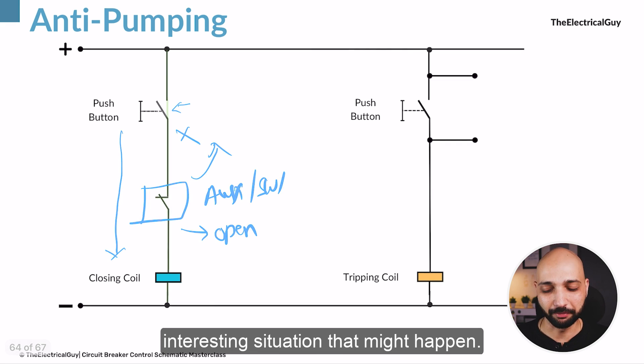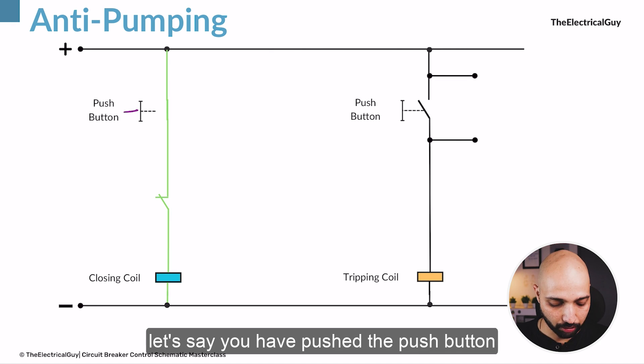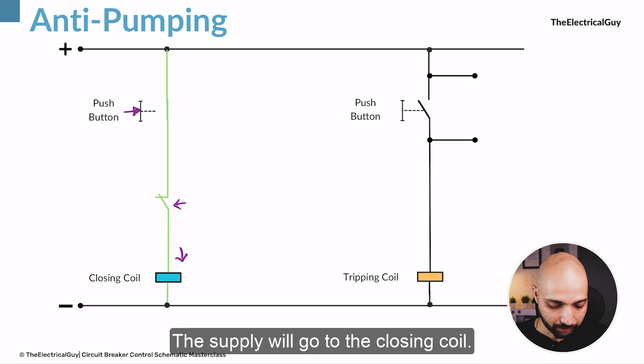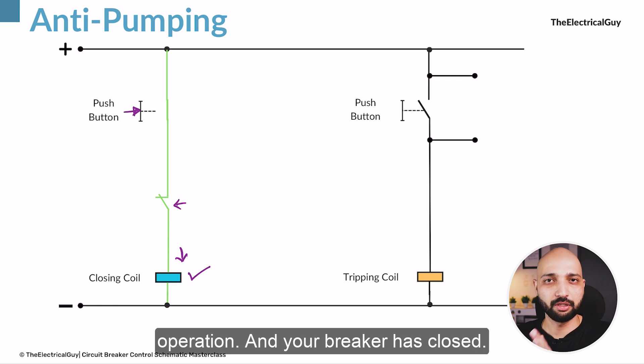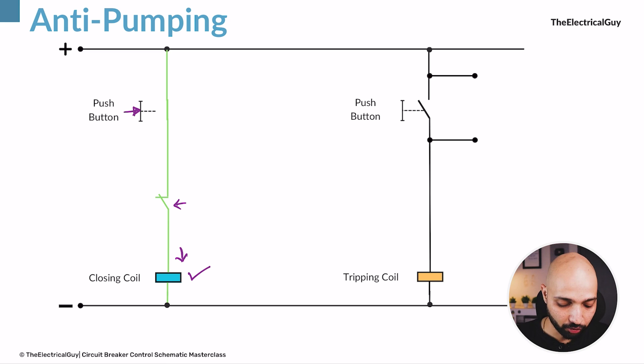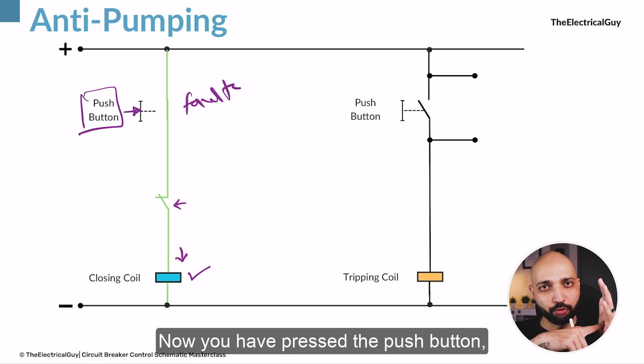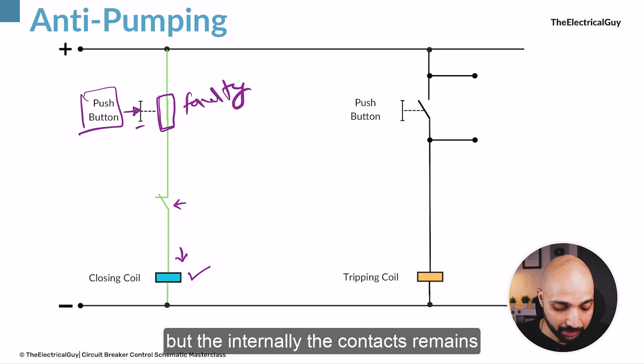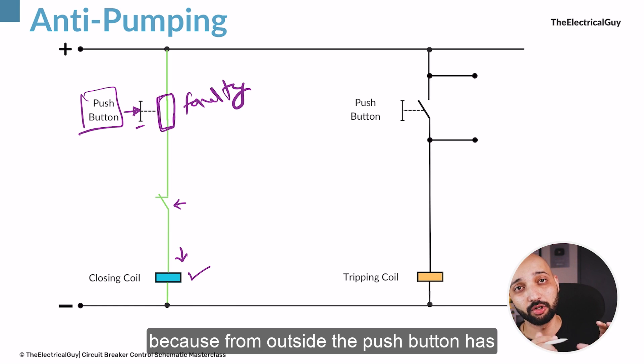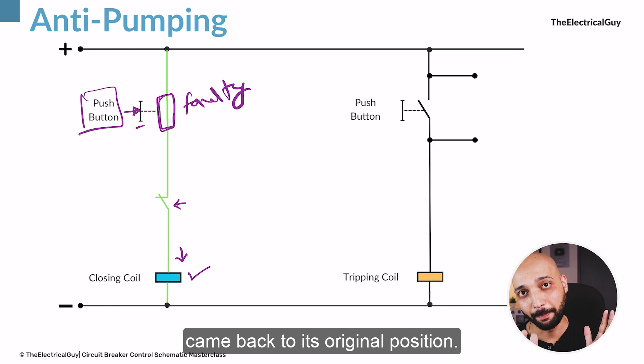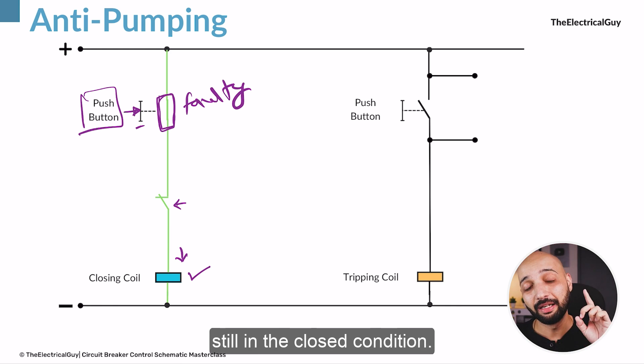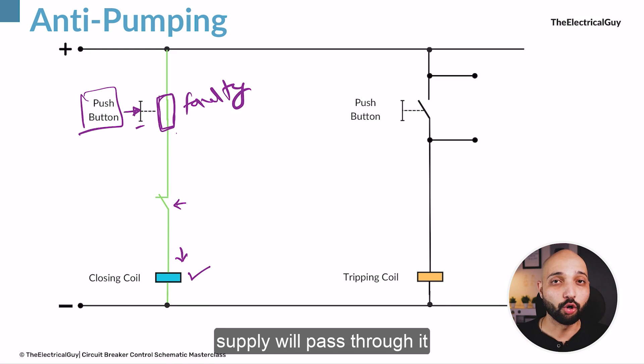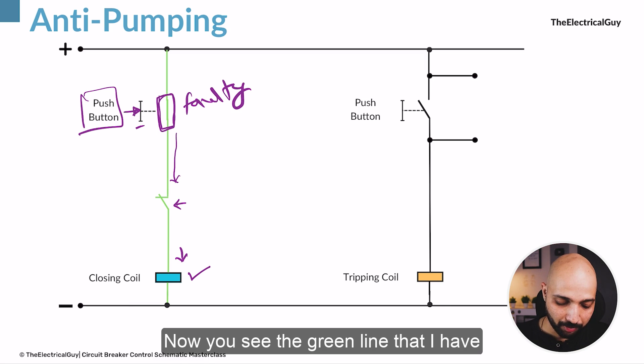Now let's talk about the interesting situation that might happen. You have pushed the push button, the breaker is in open condition, the NC contact is closed, supply goes to the closing coil, the closing operation initiates, and your breaker has closed. Now let's say this push button is in a faulty condition — you pressed it, released your hand, and physically it came back to its original position, but internally the contacts remain in the closed condition. You cannot identify this from the outside because externally the push button returned to its position, but internally the contacts are still closed, so supply will always pass through it.